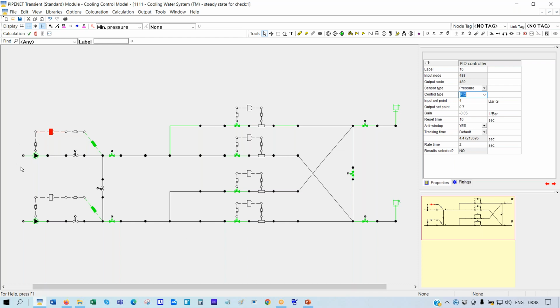So pump failure, see, when the pumps lose power, they will actually act as resistors in the system, because the fluid is trying to keep the pump rotating, and it's like dragging somebody, you know, and the pump says, oh, I want to stop, I've lost power.